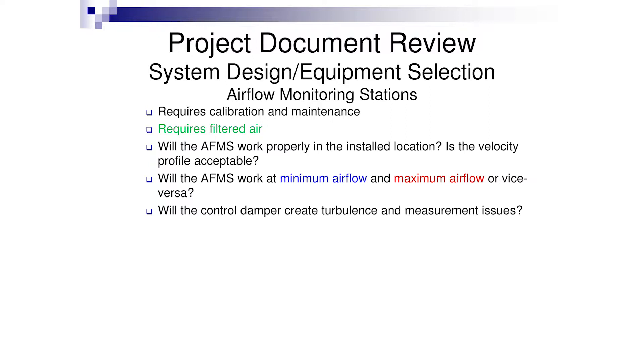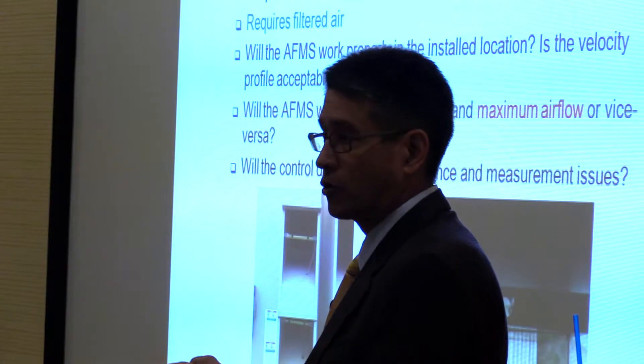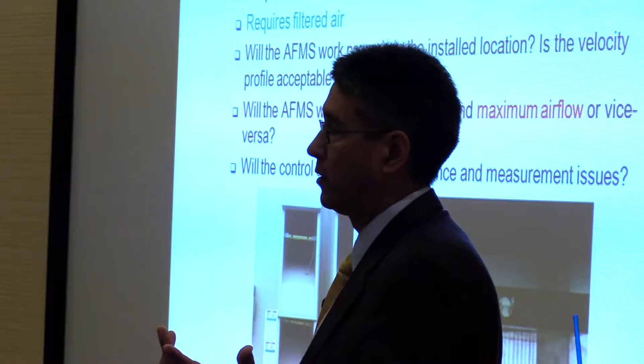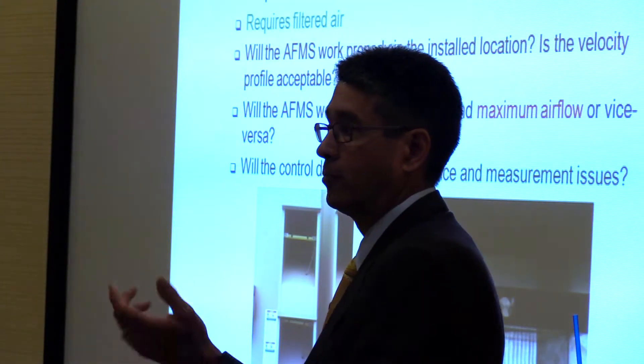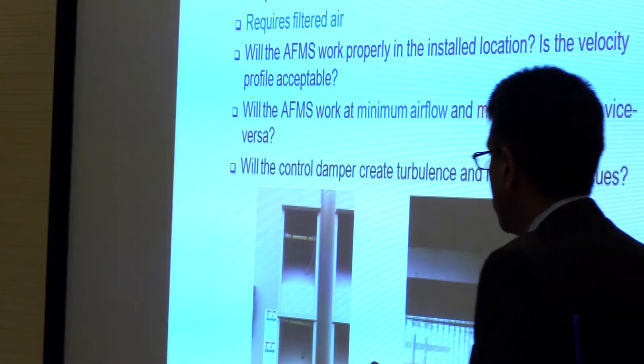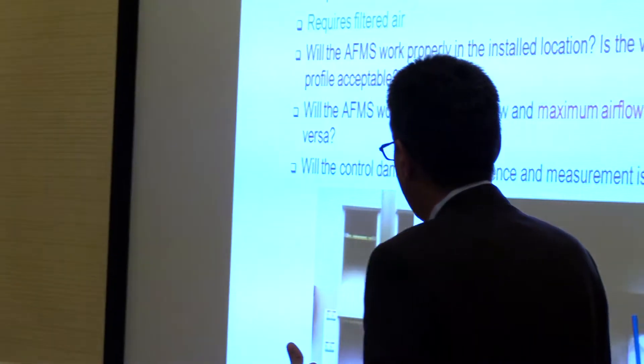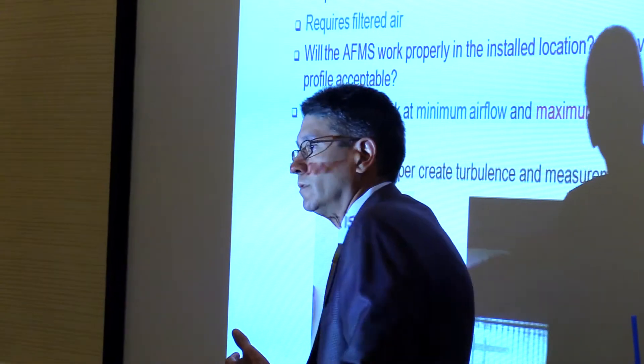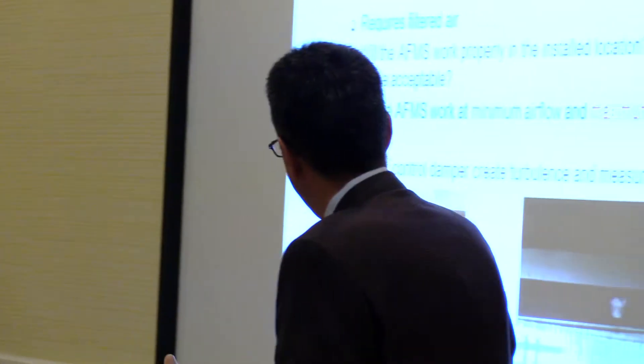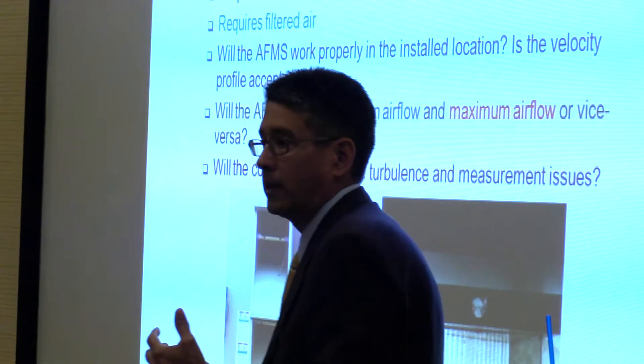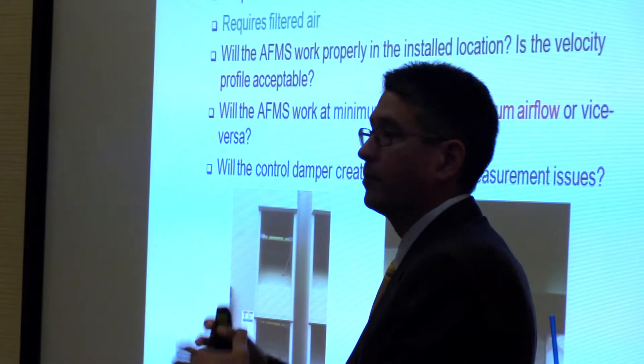Air flow monitoring stations — we're seeing the use of these quite a bit now. They give us a lot of flexibility for measuring airflow, controlling systems, reporting outdoor airflow, and controlling building pressure. The big thing is making sure they're applied and installed correctly. This is the intake of a rooftop unit — minimum outdoor air — at a health center in southern Iowa sitting on a roof in the middle of a farm field facing due north. They were having building pressure problems because their minimum air dampers were going up and down, and water had gotten into the tubing.